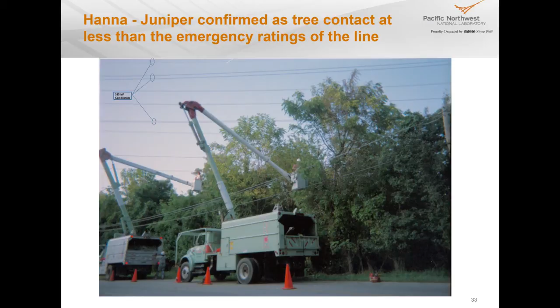And what was very, very interesting to us in the investigation, see if my laser pointer works, is that limb is dead. This isn't the first time that this line had tripped due to that tree. And the crew actually witnessed it fall on that afternoon. And I don't want to disparage any interns here, because I might be surrounded by folks that intern places, but it was fascinating in the transcripts. An intern at First Energy called into the control center saying, hey, I just saw a line fault out. You might want to know about that. Now remember, the operator, their alarm processor wasn't working.